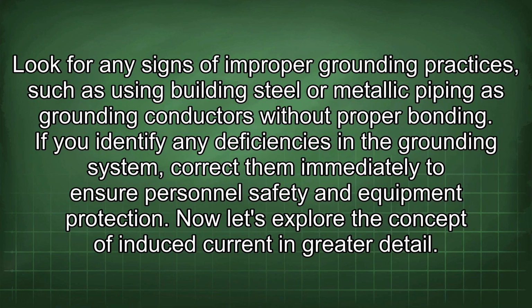Look for any signs of improper grounding practices, such as using building steel or metallic piping as grounding conductors without proper bonding. If you identify any deficiencies in the grounding system, correct them immediately to ensure personnel safety and equipment protection. Now let's explore the concept of induced current in greater detail.